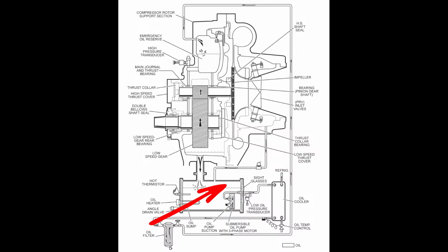So there's a few things that I want to look at. One, actually, before we get into that, the temperature sensor itself. I want to verify my oil temp sensor. It depends. This one shows it on the back. A lot of them, it's going to be up here on the front plate where the pump is. You'll have your temp sensor there where we can monitor sump temperature. Okay. So I do want to keep track of that.